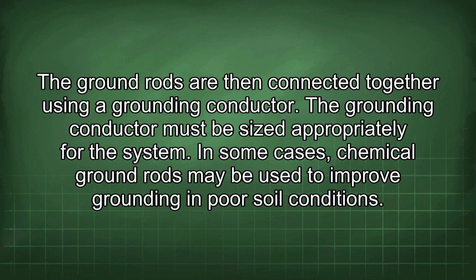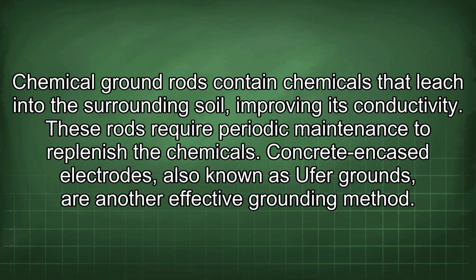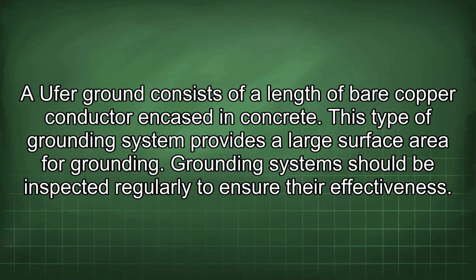In some cases, chemical ground rods may be used to improve grounding in poor soil conditions. Chemical ground rods contain chemicals that leach into the surrounding soil, improving its conductivity. These rods require periodic maintenance to replenish the chemicals. Concrete encased electrodes, also known as Ufer grounds, are another effective grounding method. A Ufer ground consists of a length of bare copper conductor encased in concrete. This type of grounding system provides a large surface area for grounding.